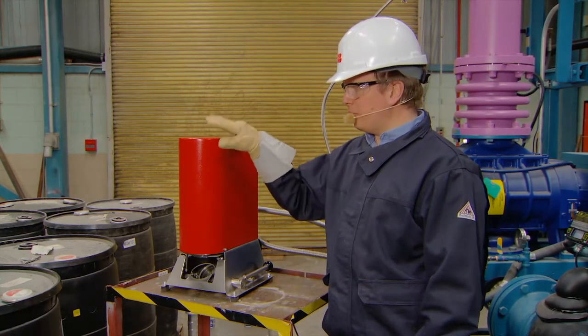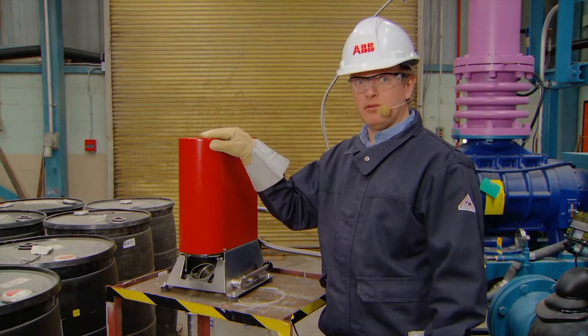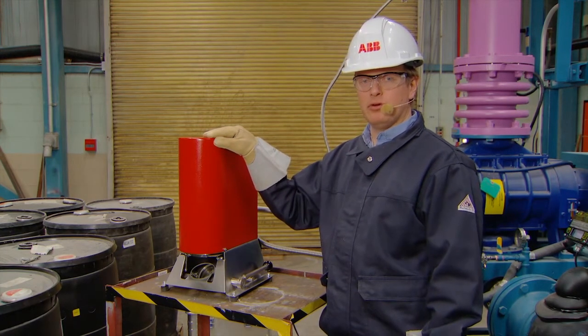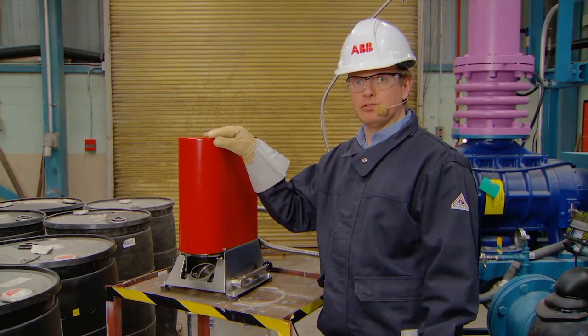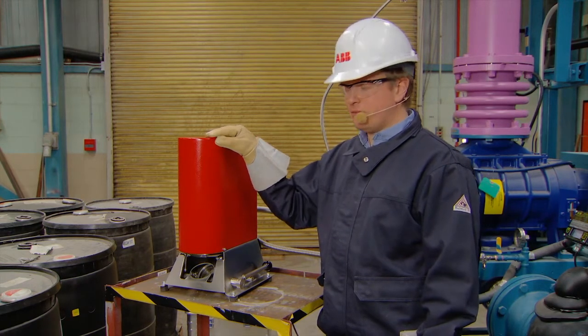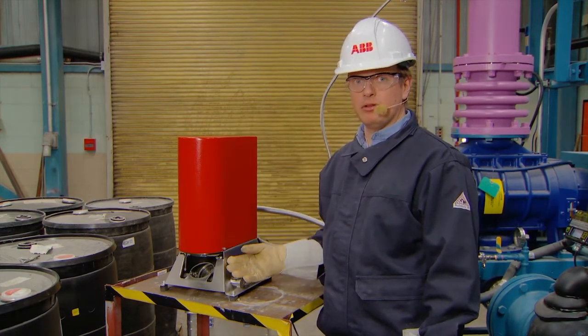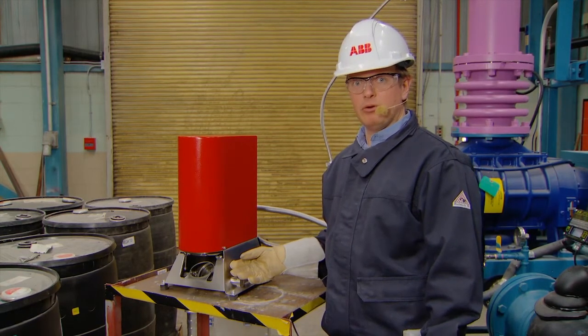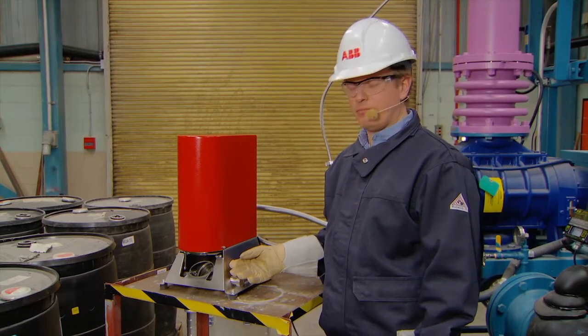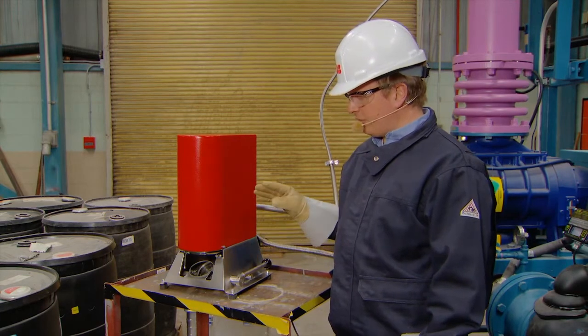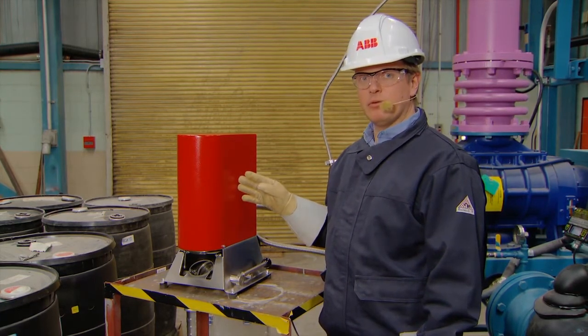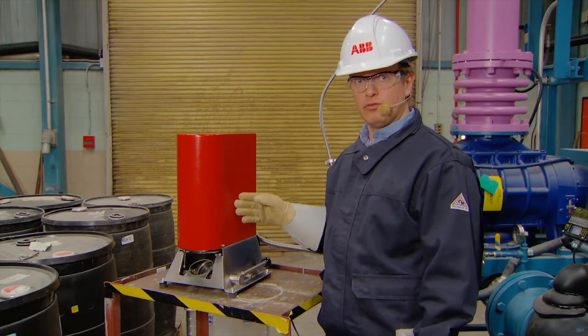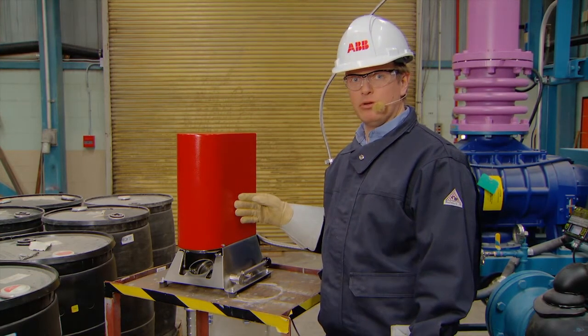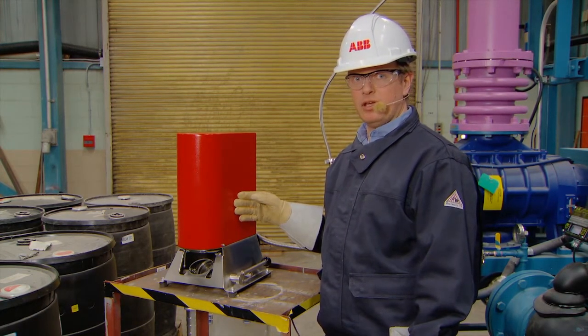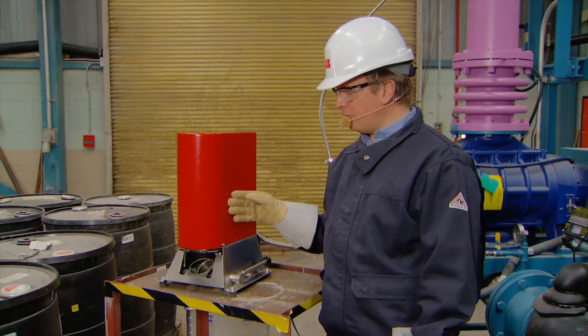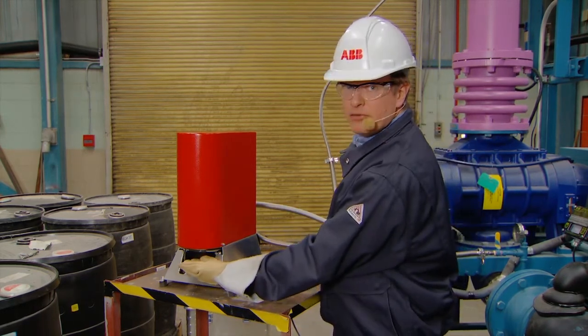This is the VZ406. It's a water measuring device used for measuring how much water is coming out from the transformer. Its purpose is to be able to determine the total amount of volume extracted and the momentary extraction rate. It has a vacuum chamber inside from which moisture is reduced, and it's reduced through a powder called phosphor pentoxide contained in a container. This container is located under the device here.